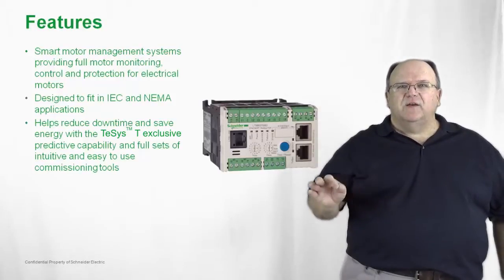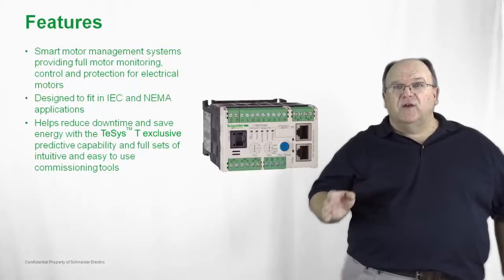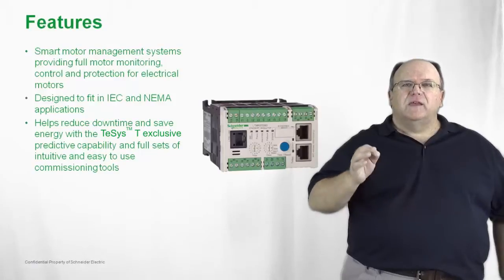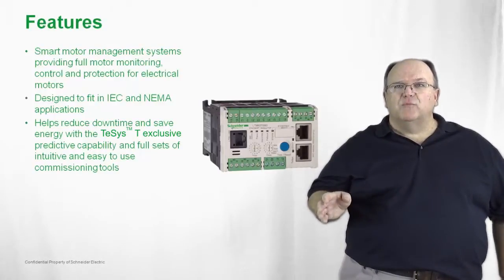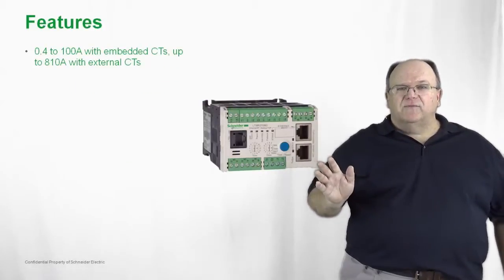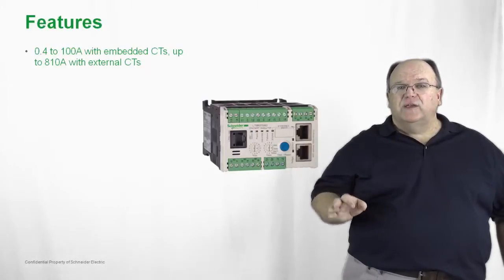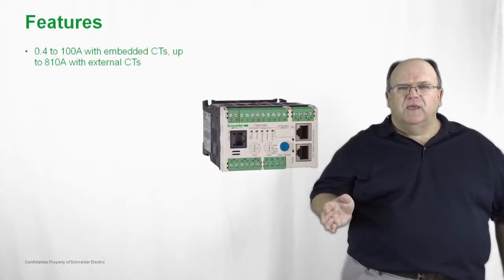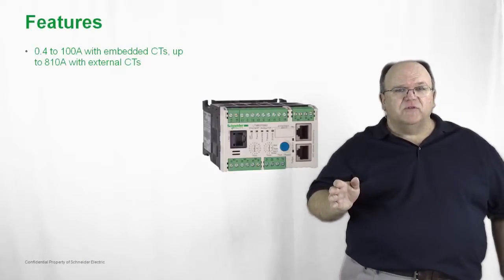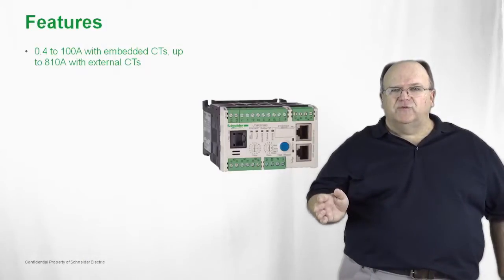It has a complete set of programmable functions. It also has pre-alarms that can be set so that you can set up and use this in conjunction with a predictive motor management system. The product itself consists of a core base that has pass-through current transformers in the base of the product for applications up to 100 amps. Above 100 amps, you would use the TeSys T in conjunction with external current transformers.